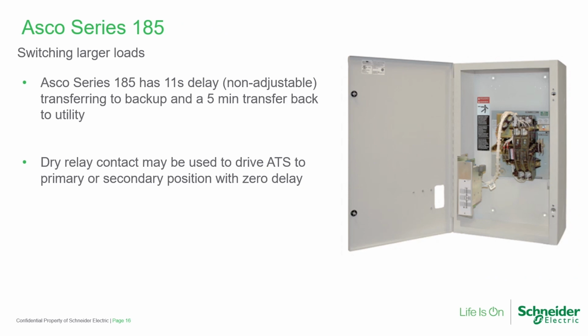The ASCO Series 185 is the most cost-effective option that ASCO offers for automatic transfer switch. It has an 11-second delay transferring to backup and then a 5-minute delay transferring back to utility. However, a dry relay contact can be used to drive the auto transfer switch to the primary or the secondary position with zero delay.